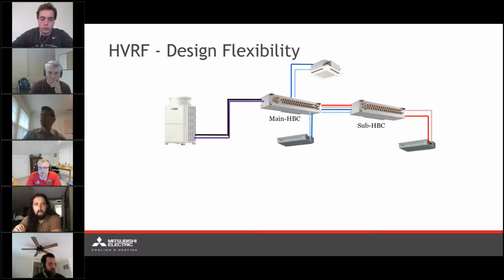Similar look to a standard heat recovery system, adding a sub HBC controller. So a sub BC or an expansion controller. Except one thing of note, we're going to have 4 pipes of connection between these two units. And this is going to be water piping, not refrigerant piping connecting the main and the sub HBCs. And it's 4 pipe at that point because we're essentially going to be acting as a 4-pipe chiller, simultaneous heating and cooling chiller between the main and the sub HBC.